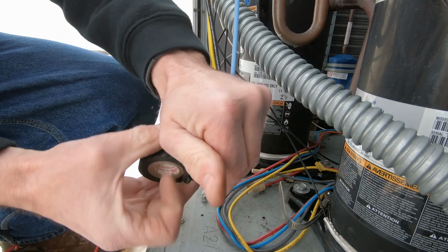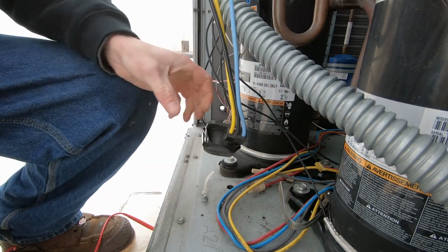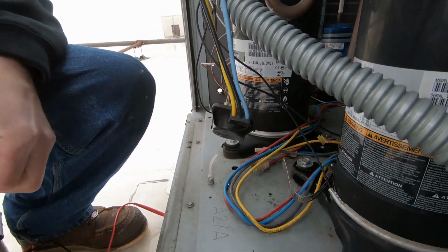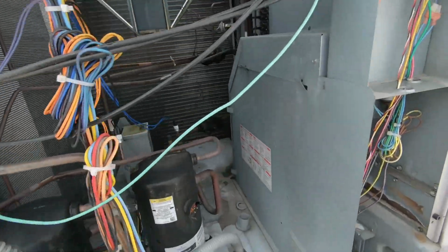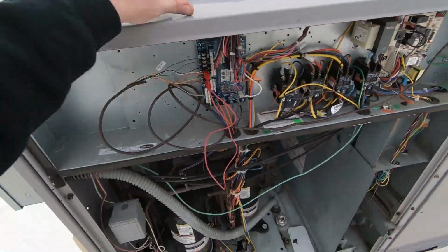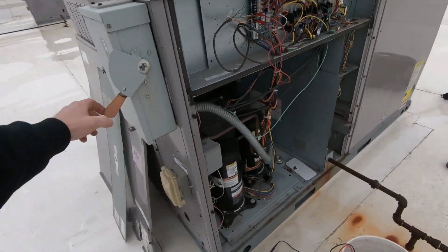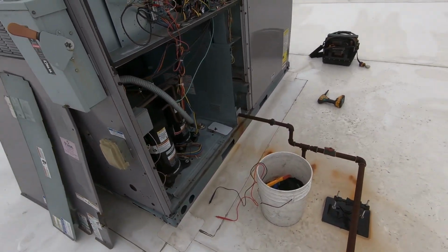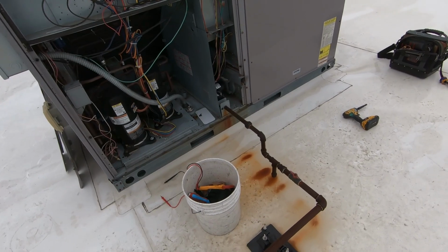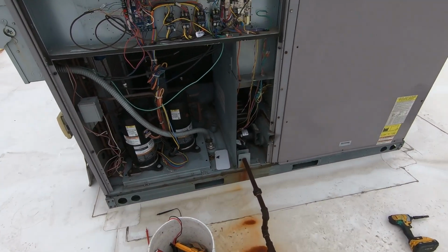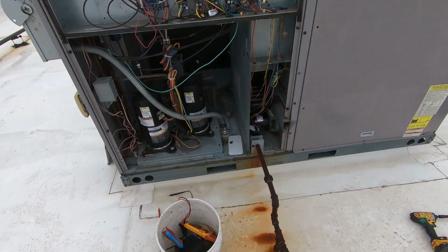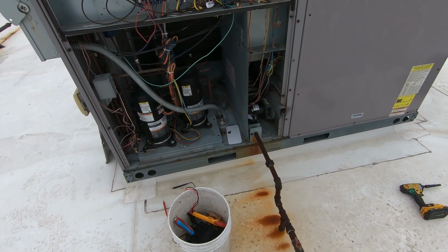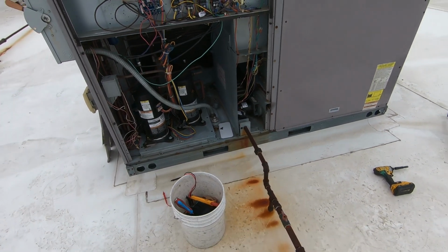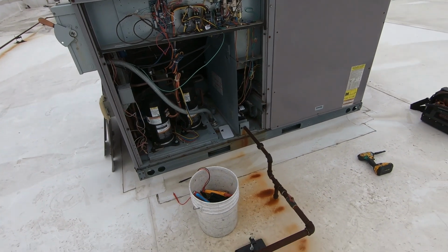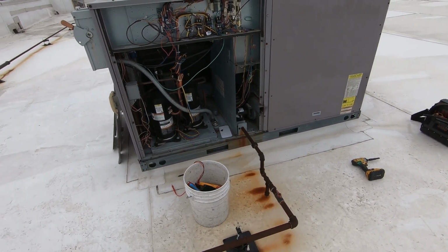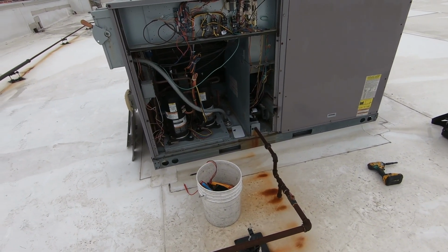Look at that. That's good. All right. I'm not even going to check for voltage in the disconnect. I'm fairly confident that that was the right breaker. And there we go. I'm just standing back because the breaker was off. And like I said, everything tested good, but you never know. You never know.